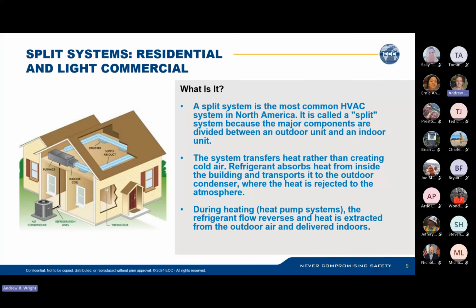All right, so split systems, residential and light commercial. What is it? A split system is the most common HVAC system in North America. It's called a split system because the major components are divided between an outdoor unit and an indoor unit. So your outdoor unit is the condenser, then inside you've got your evaporators. The system transfers heat rather than creating cold air. So refrigerant absorbs heat from inside the building and transports it to the outdoor condenser, where the heat is rejected to the atmosphere. During heating, in heat pump systems, the refrigerant flows in reverse and heat is extracted from outdoors and delivered indoors.